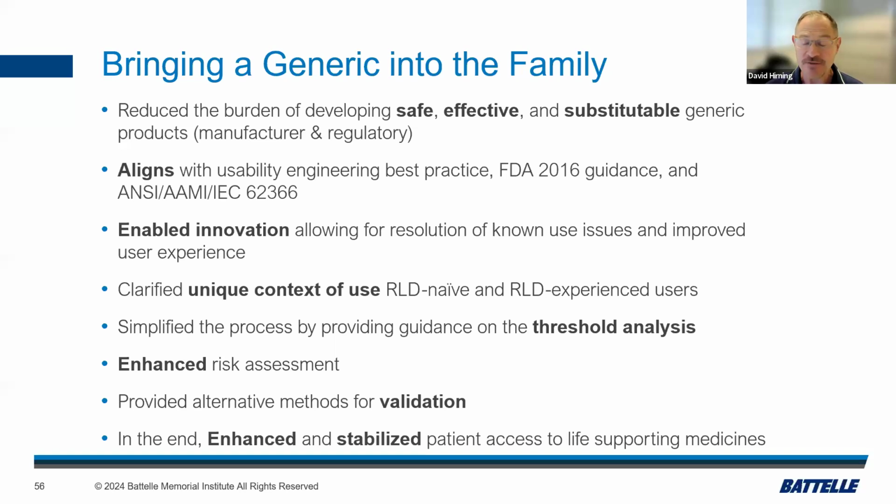Provide alternative methods for validation, and greatly simplified the requirement of a comparative use human factors study where I don't know if there's really any upper limit, but it's pretty much accepted that it's a minimum of 120 users per user group.